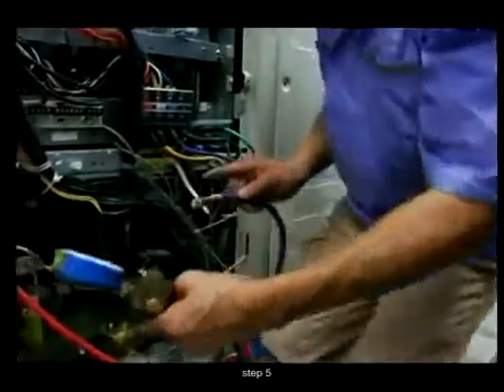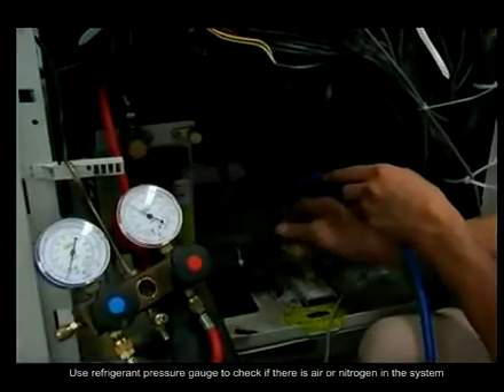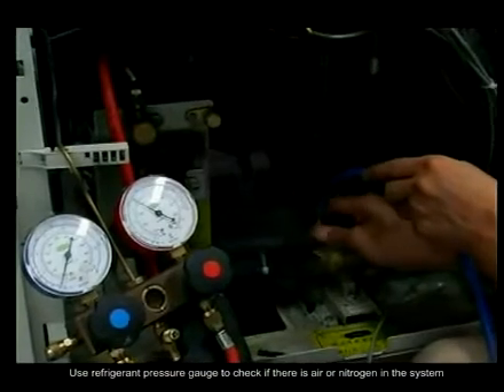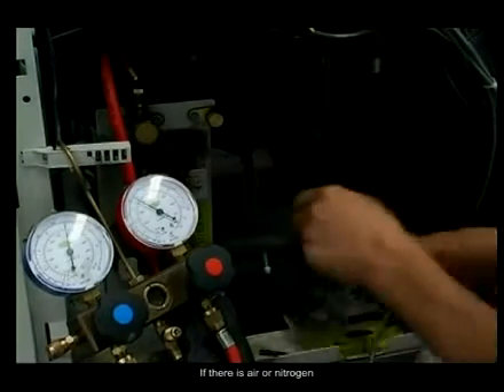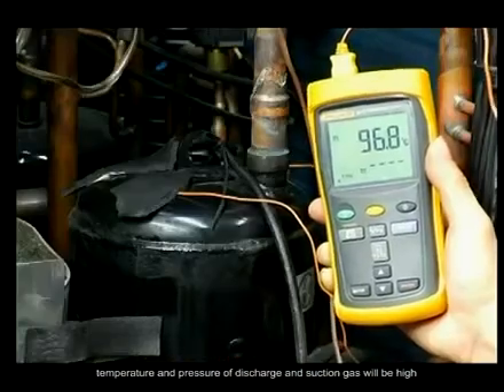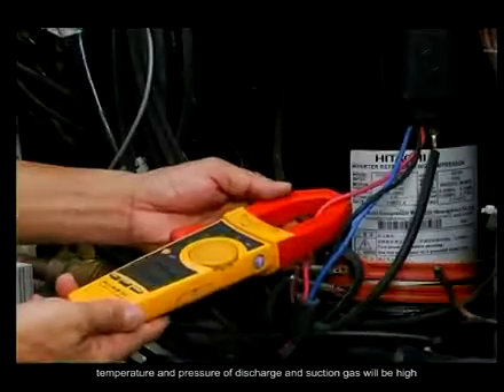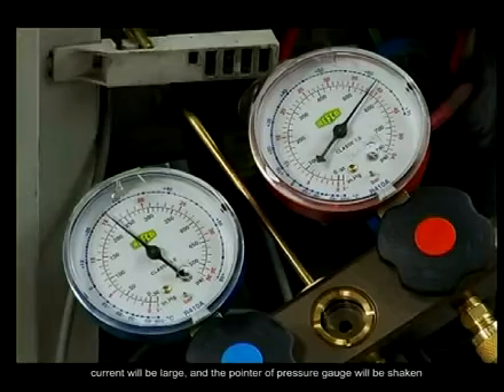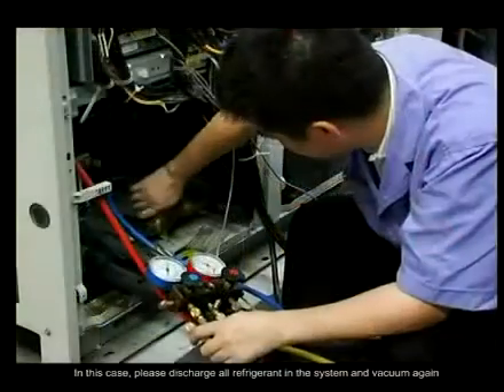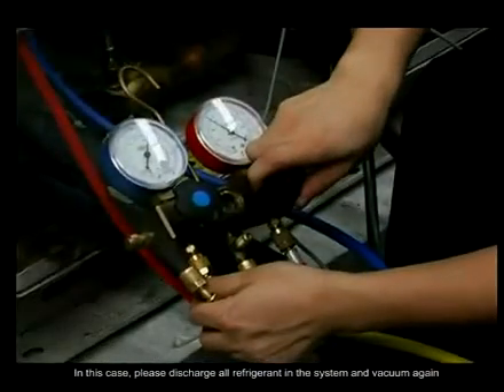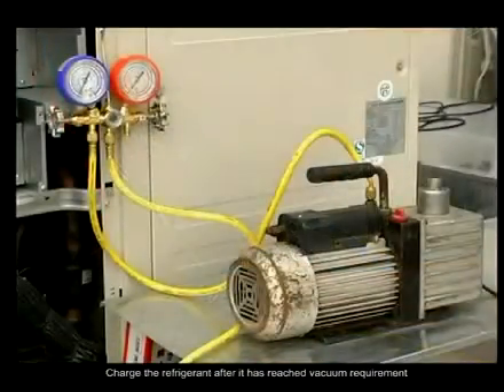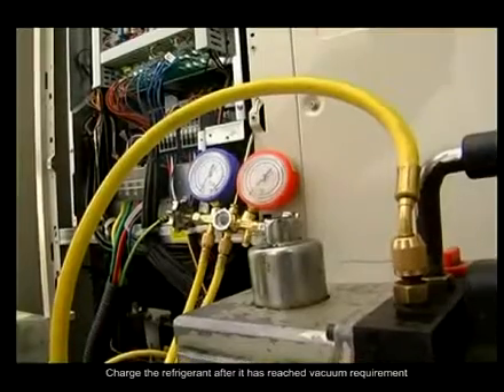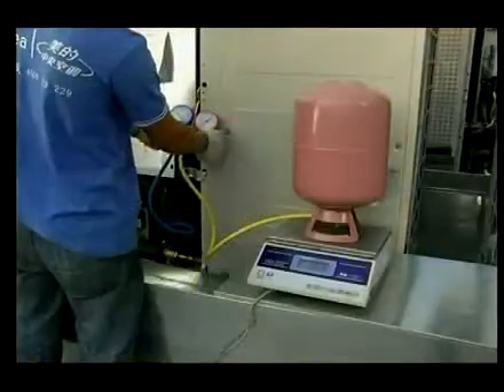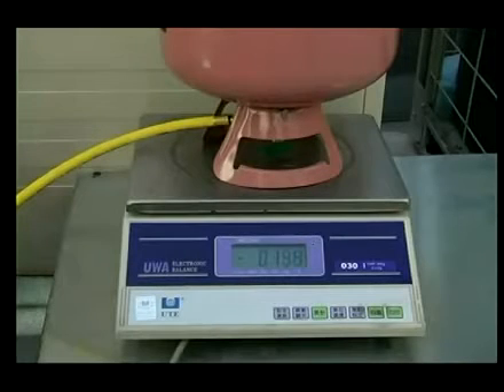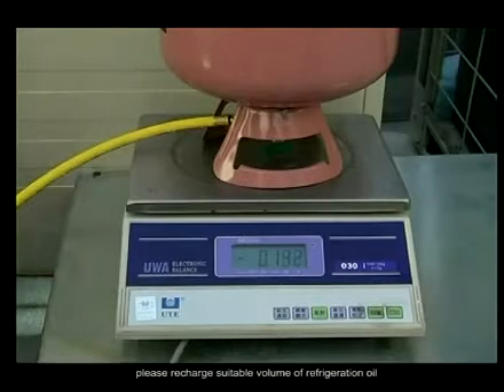Step 5. Use a refrigerant pressure gauge to check if there is air or nitrogen in the system. If there is air or nitrogen, the discharge temperature and the suction gas temperature and pressure will be high. Current will be large, and the pointer of the pressure gauge will shake. In this case, please discharge all refrigerant in the system and vacuum again. Recharge the refrigerant after it has reached the vacuum requirement. If refrigeration oil goes out during the process, please recharge a suitable volume of refrigeration oil.